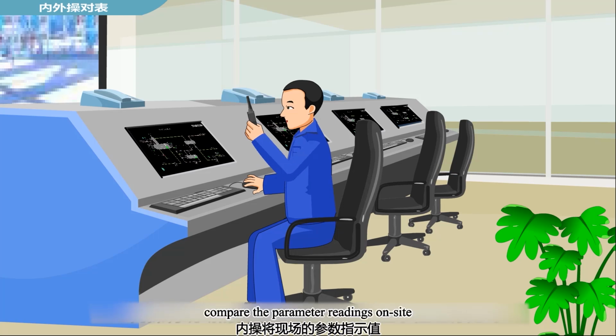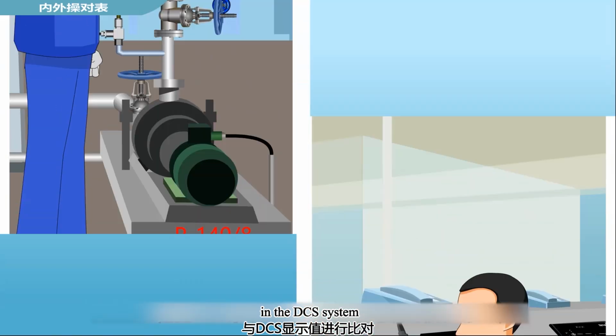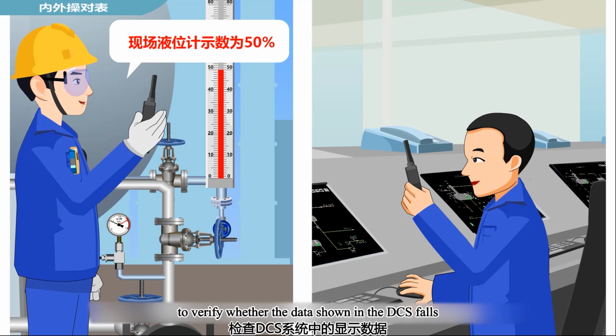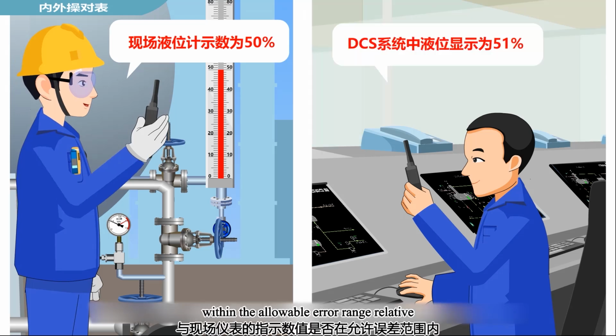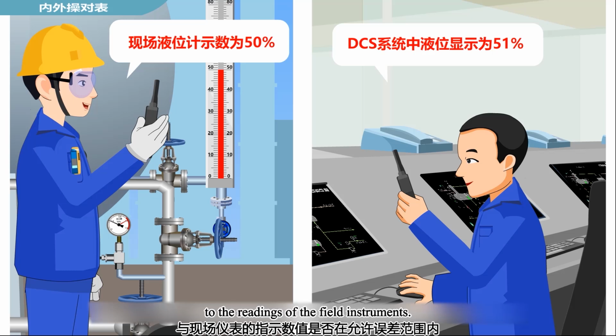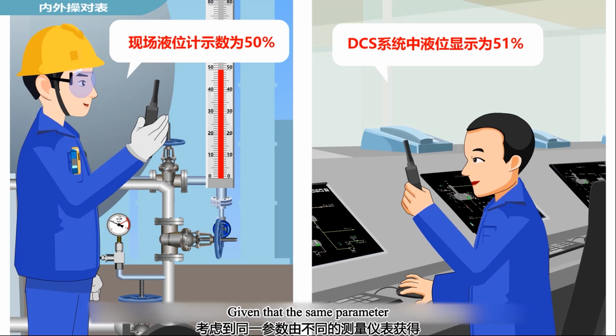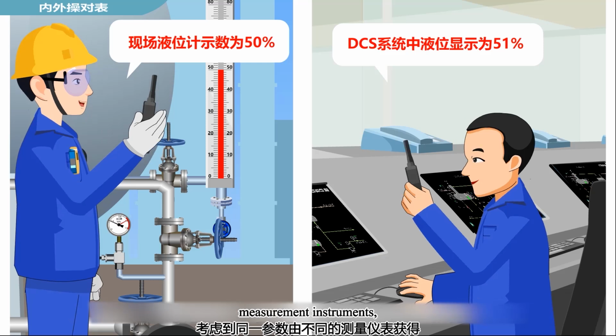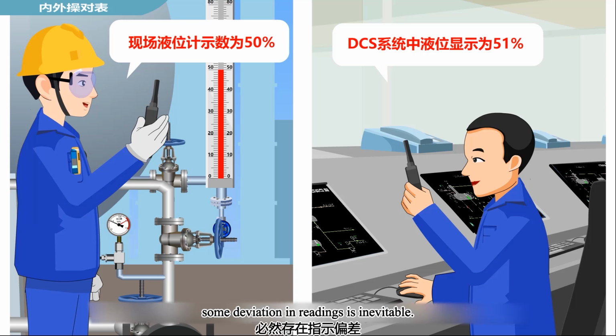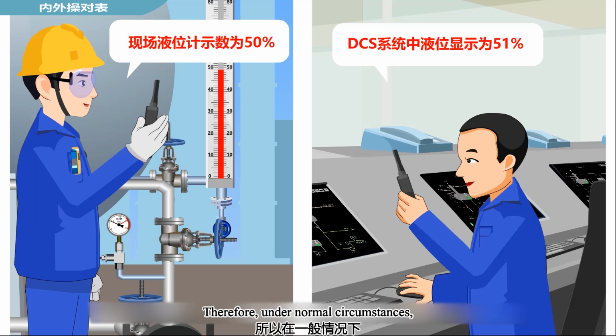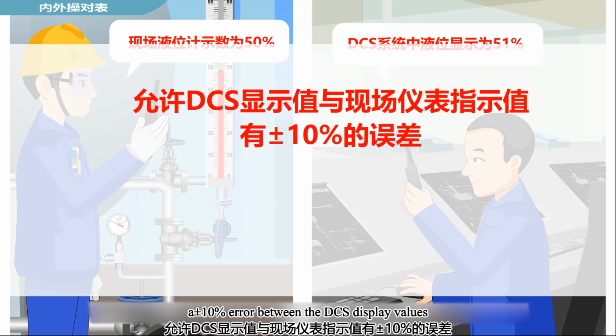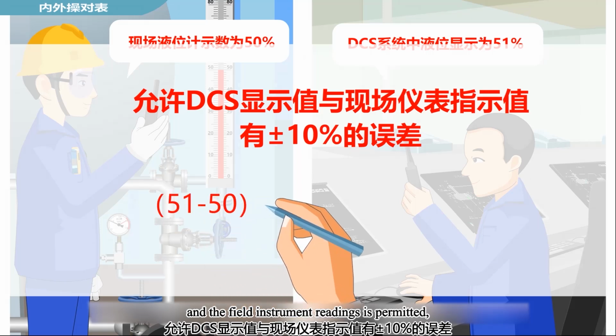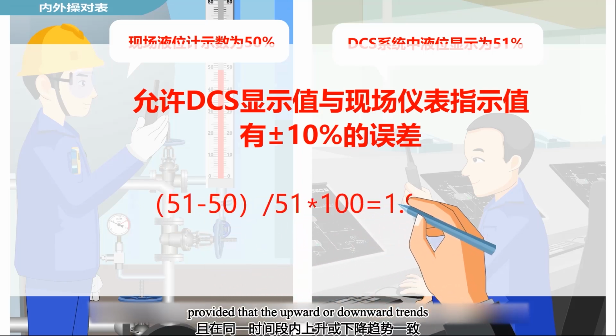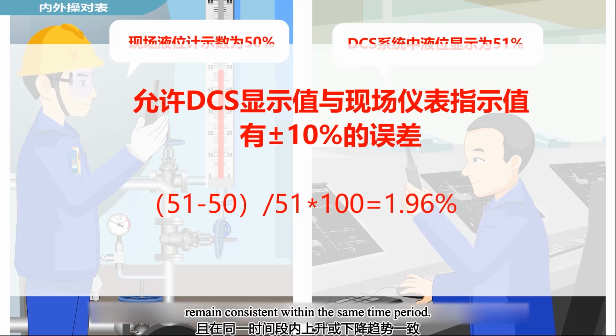Control room operator compare the parameter readings on site with the display values in the DCS system to verify whether the data shown in the DCS falls within the allowable error range relative to the readings of the field instruments. Given that the same parameter is obtained from different measurement instruments, some deviation in readings is inevitable. Therefore, under normal circumstances, a plus or minus 10% error between the DCS display values and the field instrument readings is permitted, provided that the upward or downward trends remain consistent within the same time period.